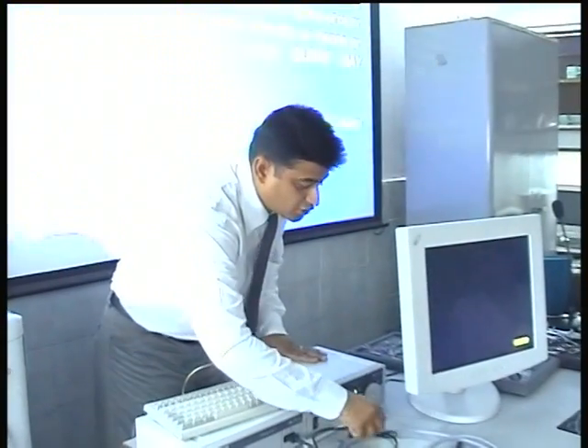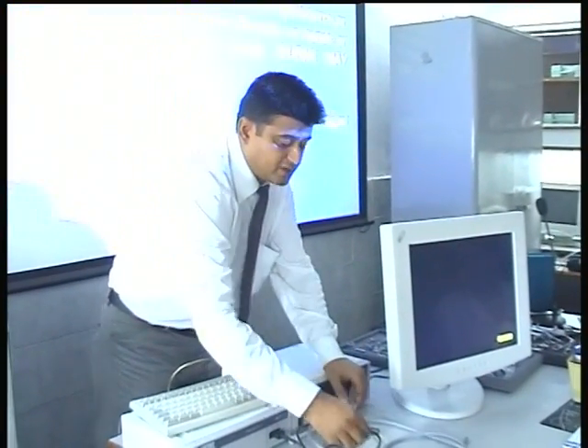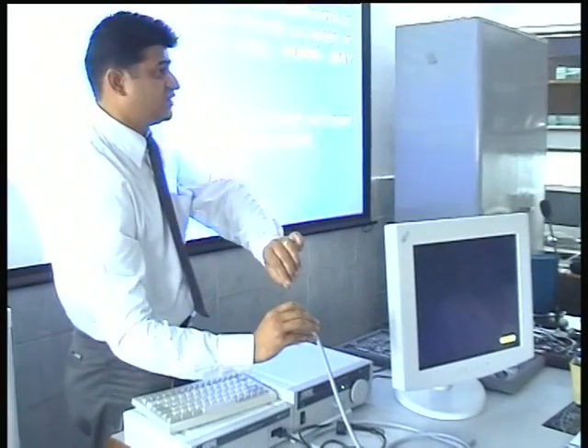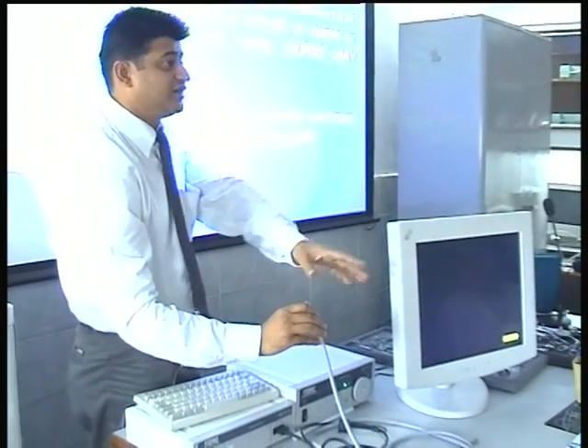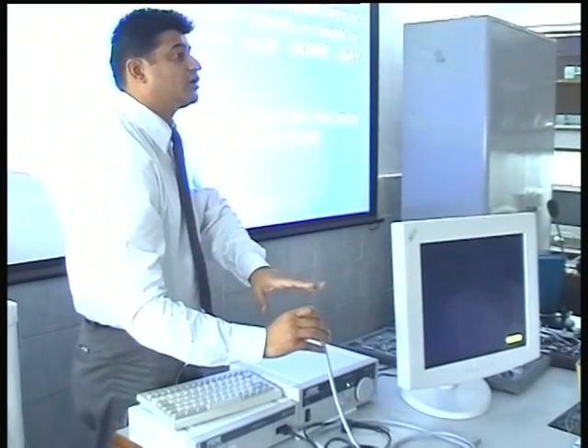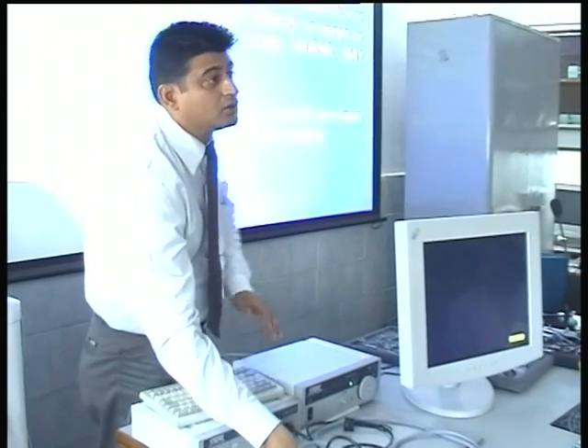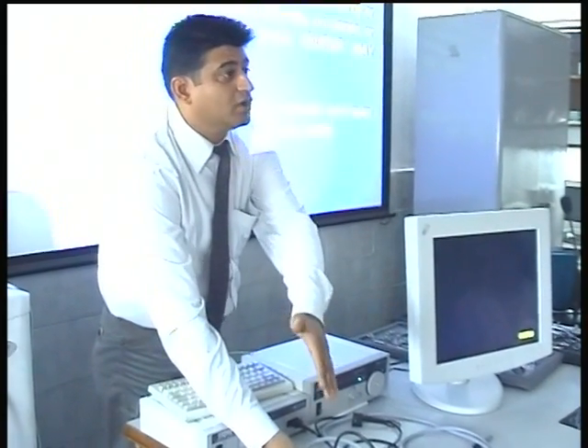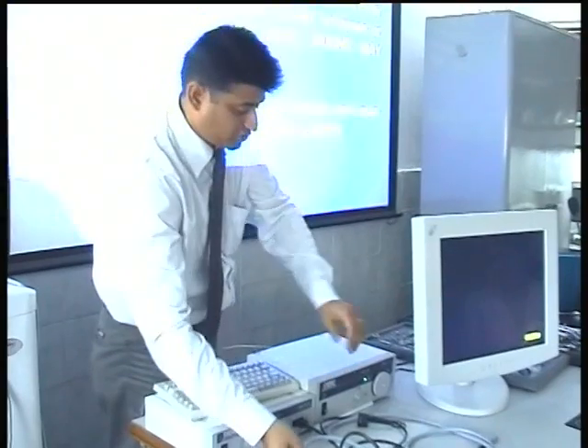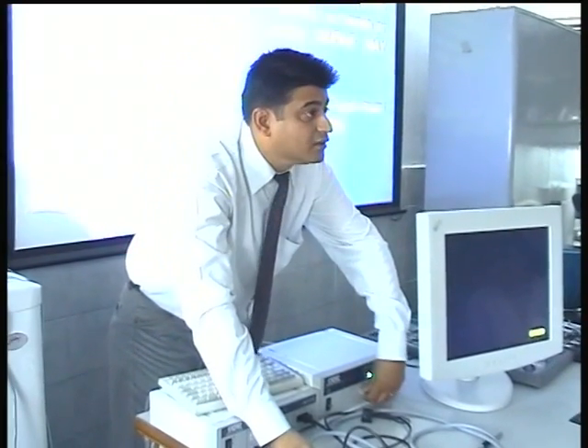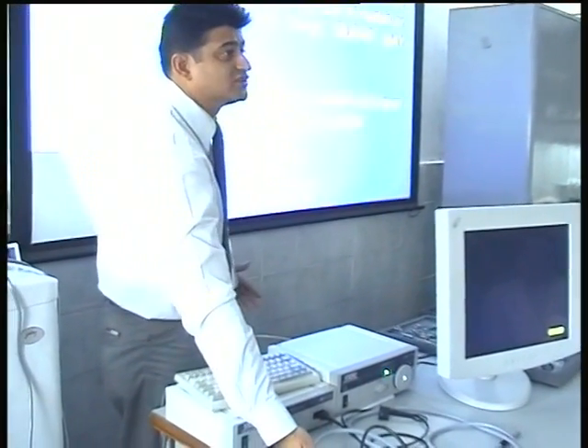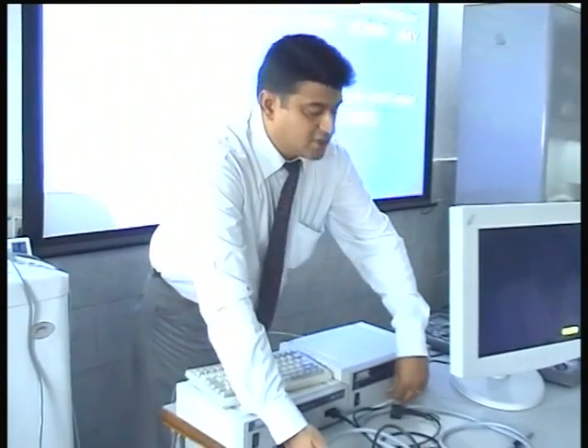And in case you are changing the scope, yes, definitely the light tries to come into your eyes. We are changing from 0 to 30 to 70 degree, and it should not hurt your eyes, or lie on the sterile drapes, because it will burn. It is a high intensity xenon light source. It is better that we reduce the light here. One person should always be at the endovision trolley, and he should reduce the light and then change over.